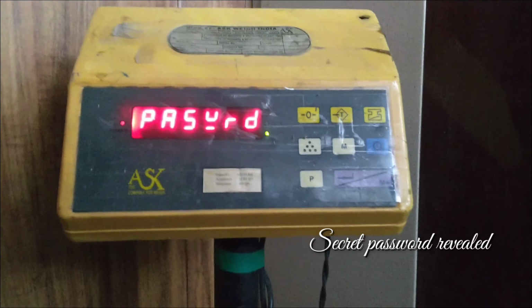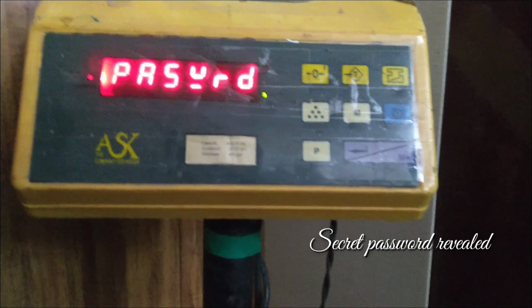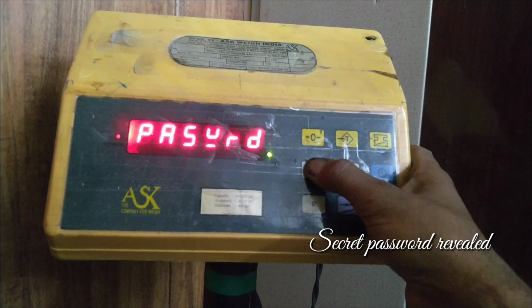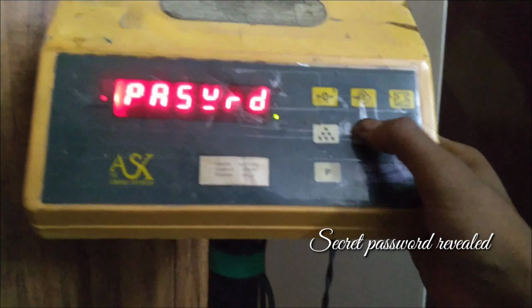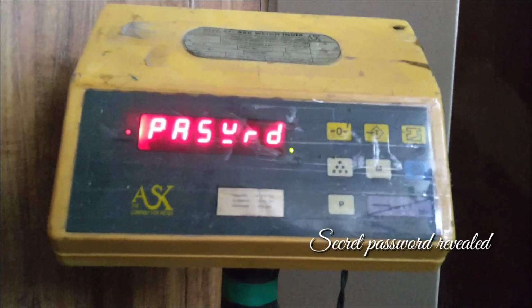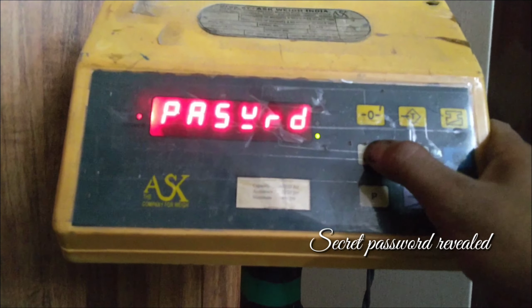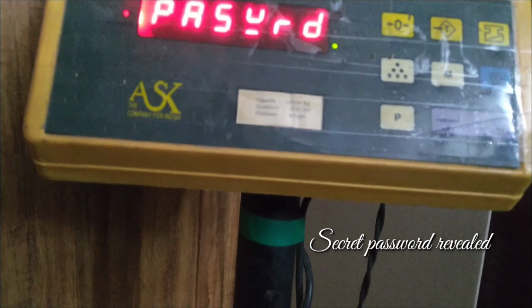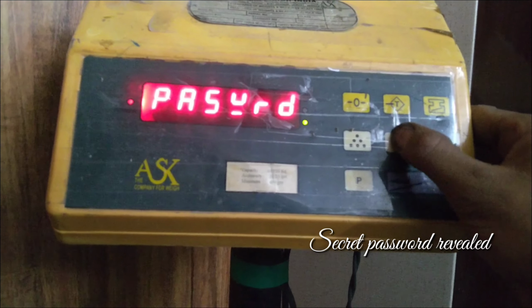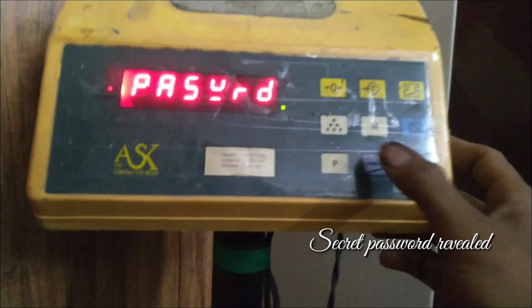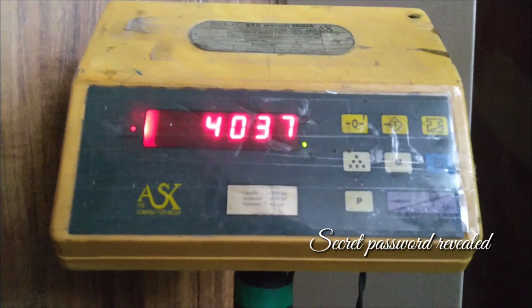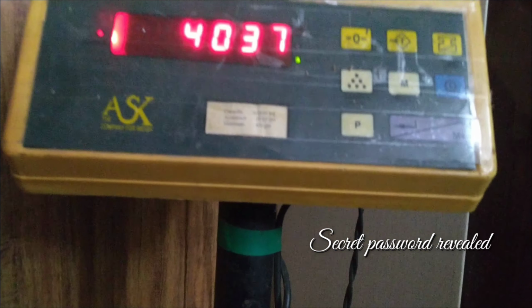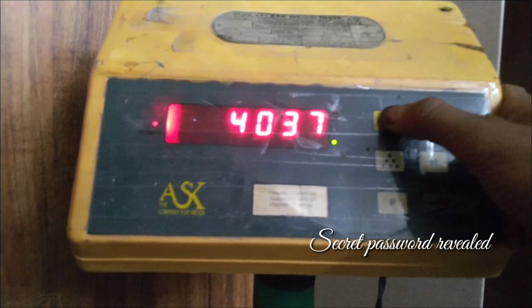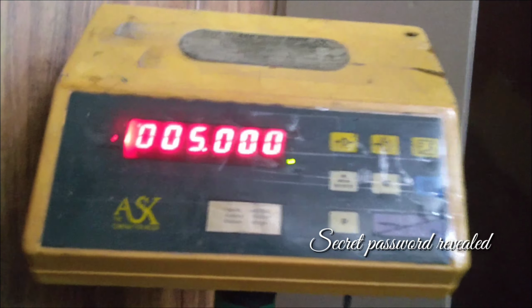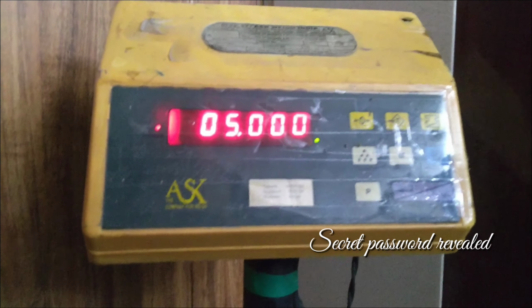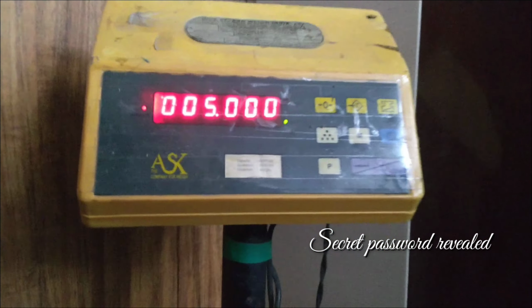Here you can see it wants password, and now we press the sample 3 times, mode, and again sample for 2 times, and mode for 3 times. Now we press the enter button. Here you can see. Now we press the 0 button from here. Here you can see it says we have to place 5 kilograms weight on the scale.